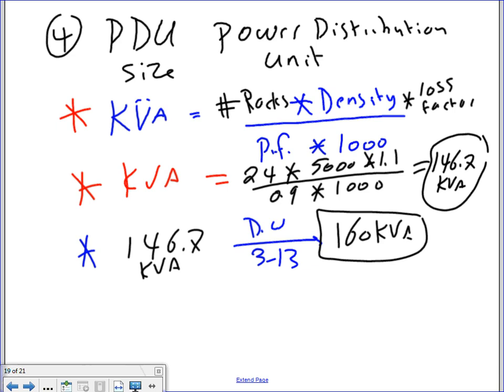Now, in real life, Karen, these sizes might be different. So you're going to go to the manufacturer. Typically, they are very close to each other. You choose the next standard. So you ask them for a 146.7 PDU, and they'll tell you, hey, we make 150. You stick with 150. Am I making sense? You go to the next standard. For the ease of the installation calculation, let's stick with these numbers that you guys have for standardization. Shall we move to 5? Or am I going too fast here?